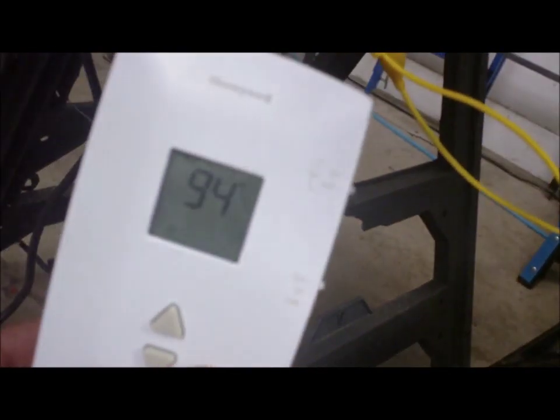Let's see if I can get something non-conductive. These two wires from here to here, that is 120 volts, and that is for your inducer draft motor. So I can try. We're going to shut it off. And there you go. That's for cooling. What I'm going to do is make a video of it calling for heating.